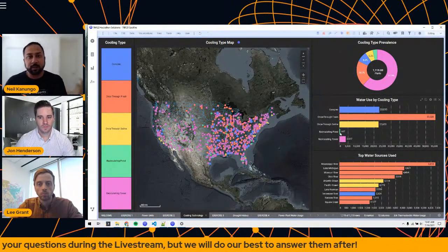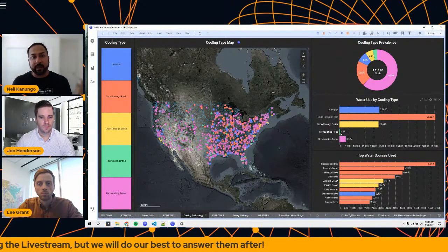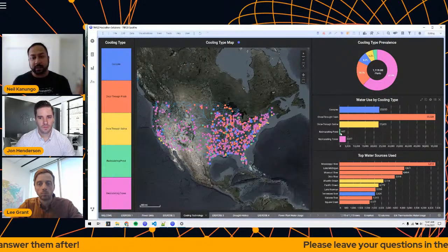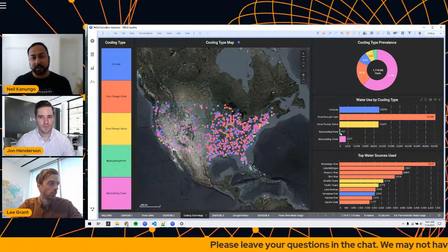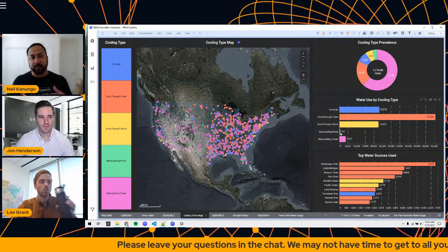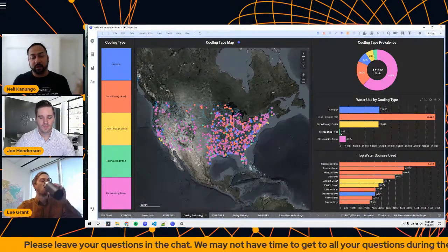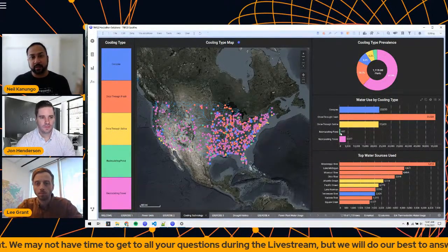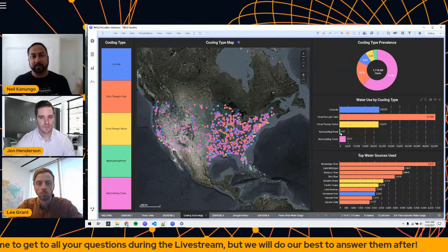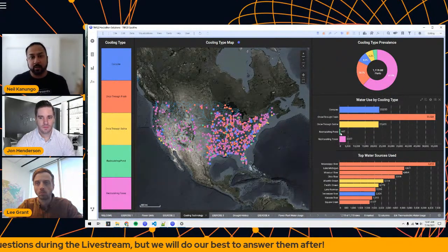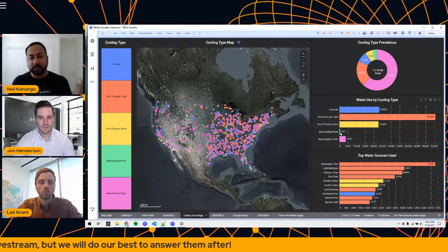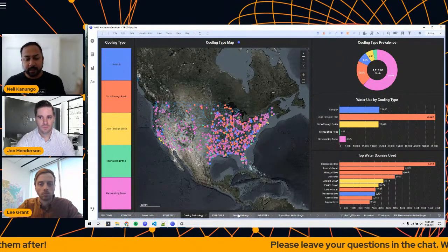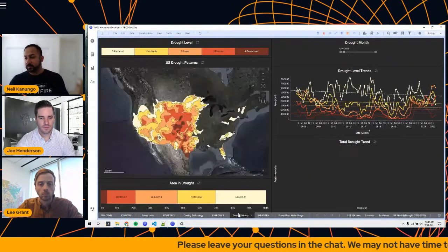So once through uses quite a bit of water, as you can imagine, because it's not reusing and recirculating that water. Recirculating doesn't have as much use, but has more evaporation that's lost overall, so it actually consumes more, while the use is the water that is entering into the plant and being used by the plant. And so once through is a very high water usage since it has to continuously feed those water cooling systems. Next was a little bit of drought history.